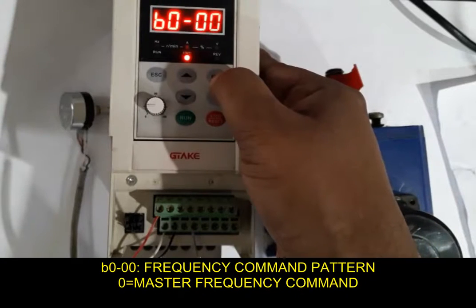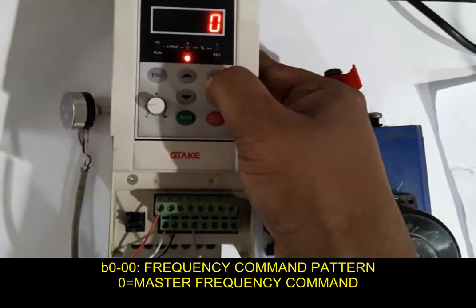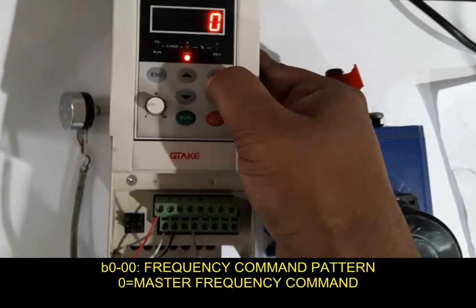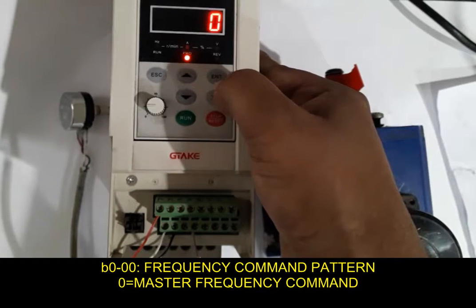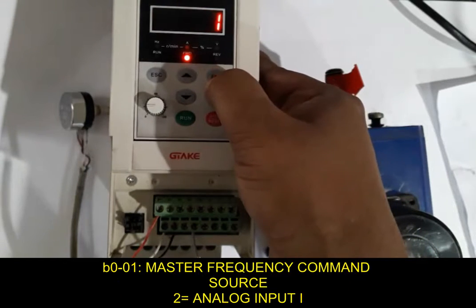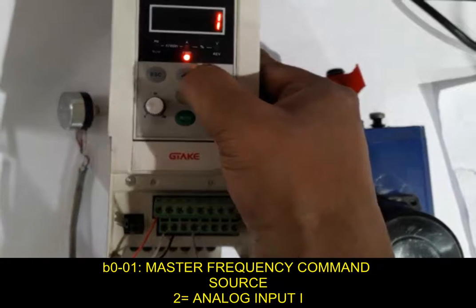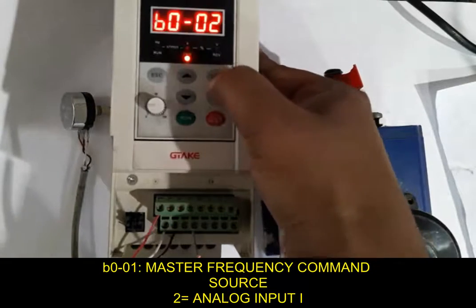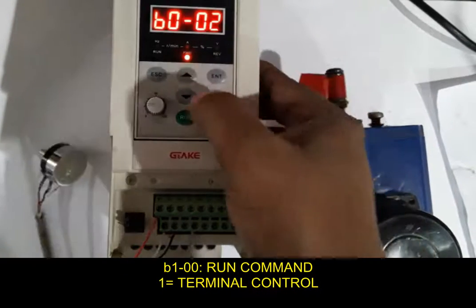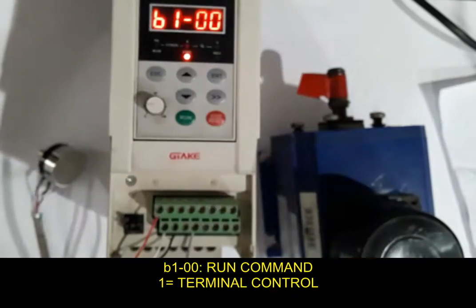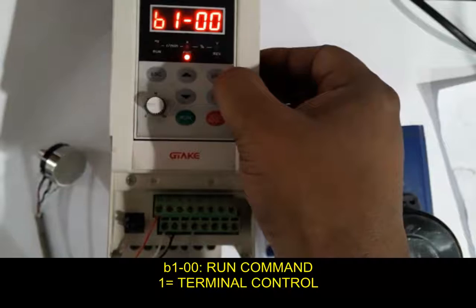In parameter B000, frequency command pattern, set here 0 for master frequency command. In B001, master frequency command source, set here 2, and B100 for run command, set here 1 for terminal control.